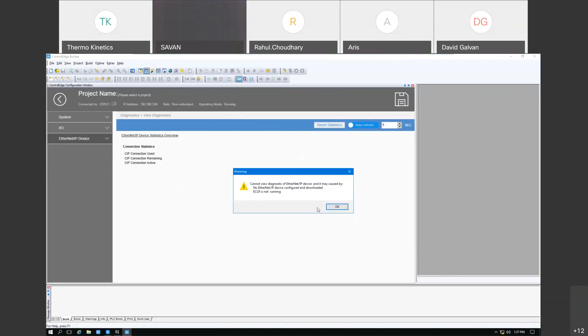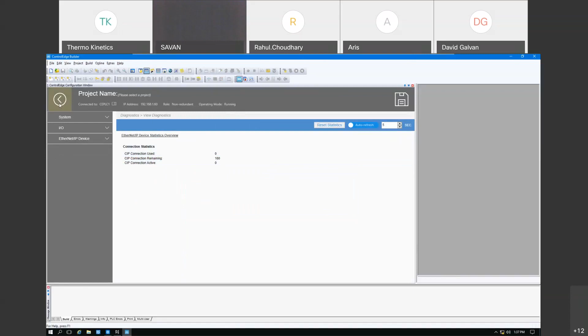Now, if I go back to my view, you have the 3 cards that I just showed you. If I have any EIP devices, they would pull up here. I do not currently have any EIP devices connected, but you would see the connection here. If I want to upgrade the firmware, I simply click upgrade firmware, and it gives me the different components of my chassis. Here I have the central processor module, the extension processor module for my remote I/O, and a UIO card. If I have a serial communication board, it'll show up there, whatever you need. Right now, everything's okay. I'm up to the 150, 151 where I need to be. My CPM is good. I'm at the latest and greatest revision, 151. If I wanted to upgrade this, you would hit upgrade and then proceed with the upgrade.